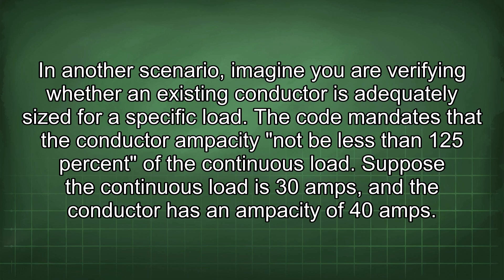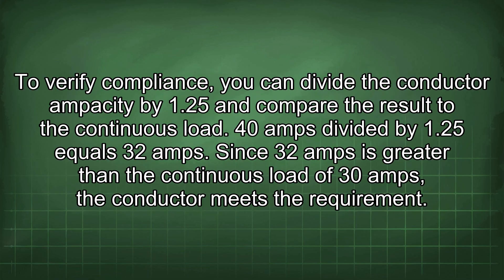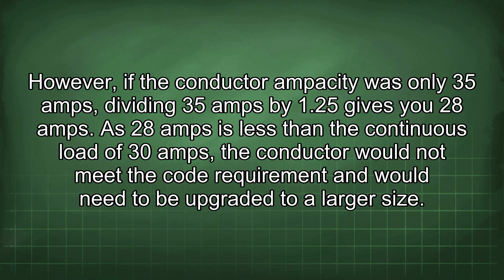In another scenario, imagine you are verifying whether an existing conductor is adequately sized for a specific load. The code mandates that the conductor ampacity not be less than 125% of the continuous load. Suppose the continuous load is 30 amps and the conductor has an ampacity of 40 amps. To verify compliance, divide the conductor ampacity by 1.25: 40 ÷ 1.25 = 32 amps. Since 32 amps is greater than 30 amps, the conductor meets the requirement. However, if the conductor ampacity was only 35 amps, 35 ÷ 1.25 = 28 amps, which is less than 30 amps, so it would not meet the code requirement and would need to be upgraded.